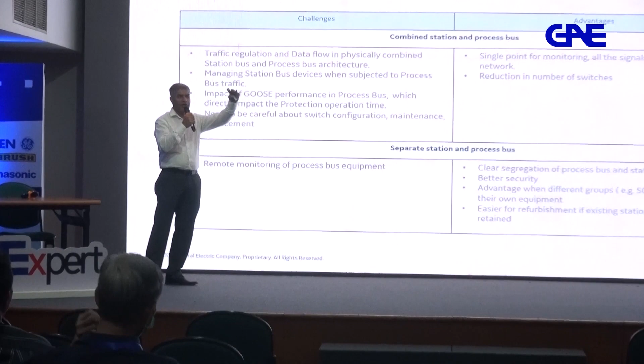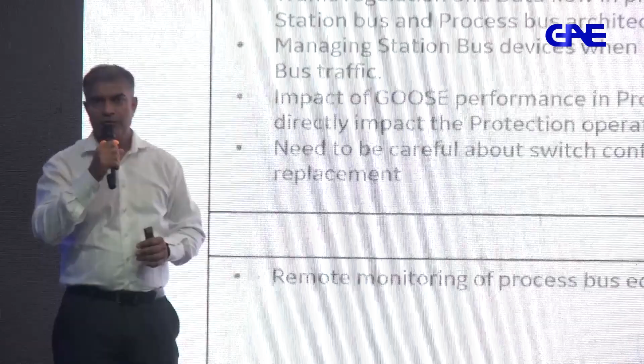But the advantage is that there is a clear segregation. Even if you don't segregate your traffic very well, you can still get away with that. It can be an advantage when different groups, like the SCADA group responsible for station level and the protection group responsible for switchyard equipment, can access their own switches. So there's segregation in responsibility and ownership, and it's easier for refurbishment if your existing substation already has a station bus.